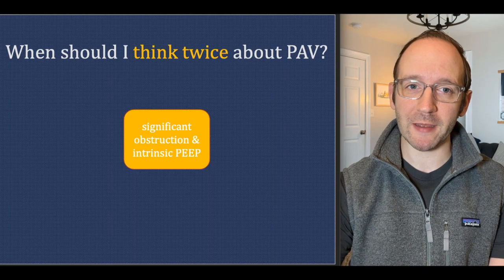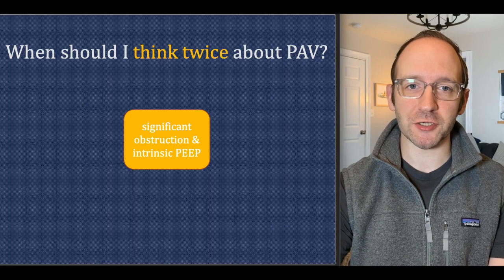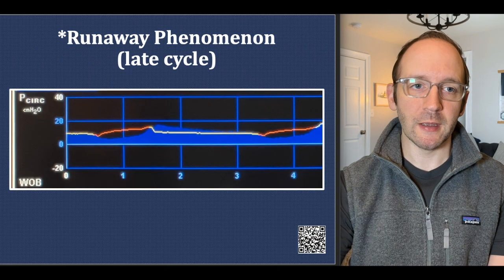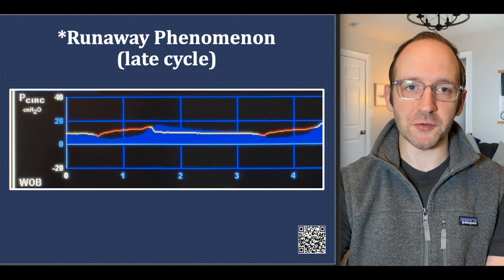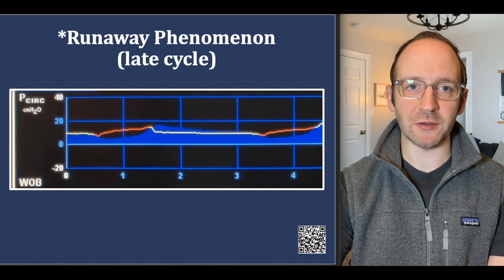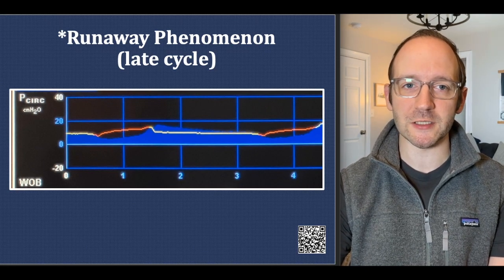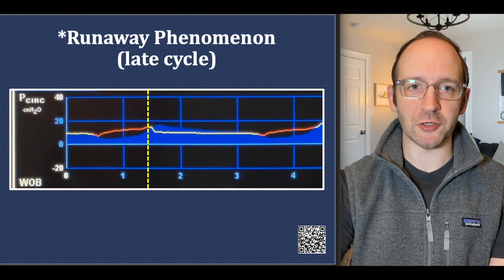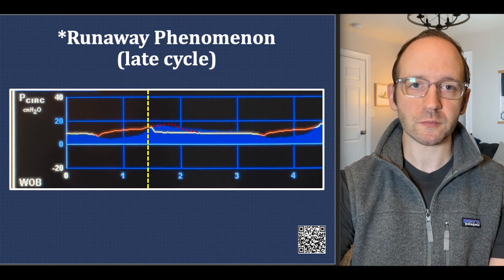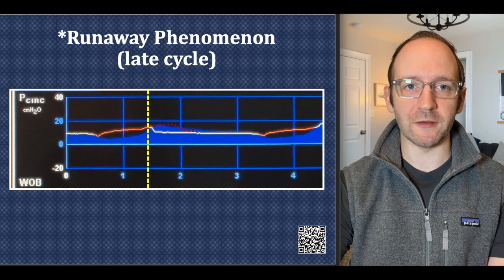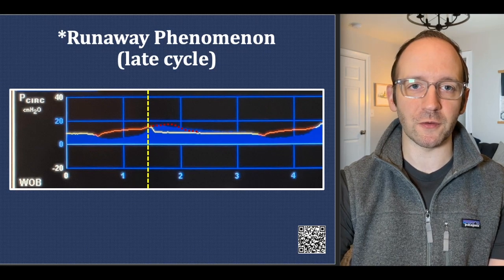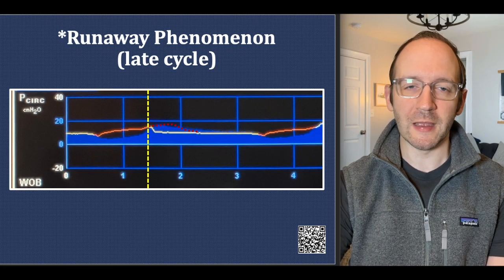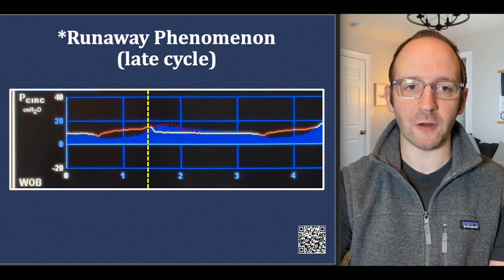When should you think twice about PAV? If there is significant obstruction and intrinsic PEEP, it can make it difficult for the ventilator to both trigger and cycle. Furthermore, with obstructive lung pathology or high resistance, you can get what's called the runaway phenomenon — a dyssynchrony specific to PAV that does not occur in other modes. The breath will continue for perhaps as long as the initial inspiratory effort. This is something you can only really see by monitoring the vent waveforms. It's not something I've seen commonly, but it has been described in the literature.